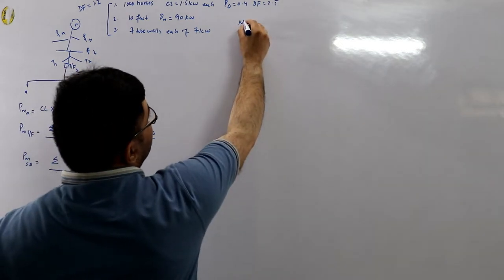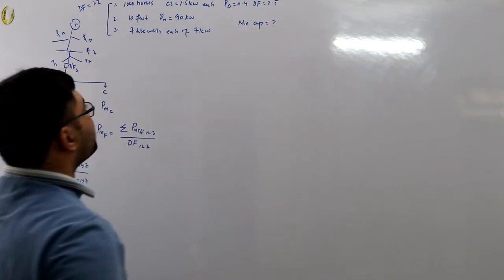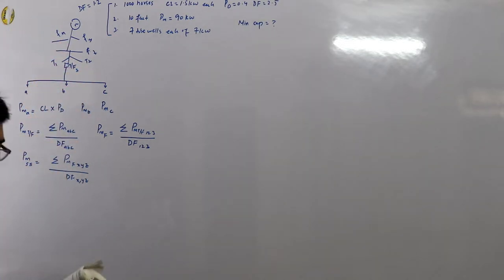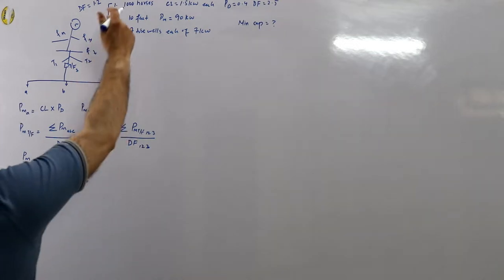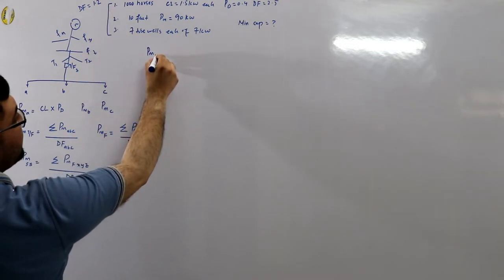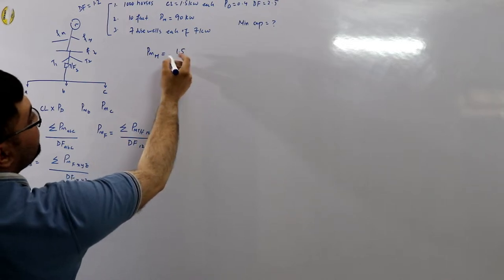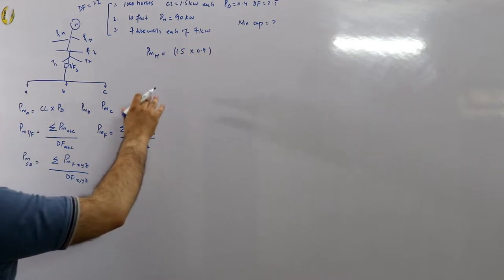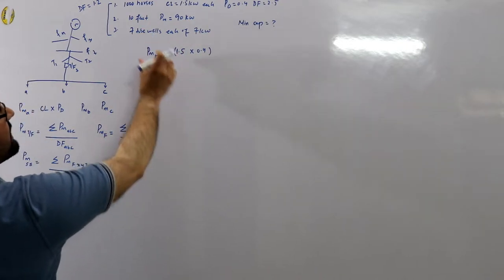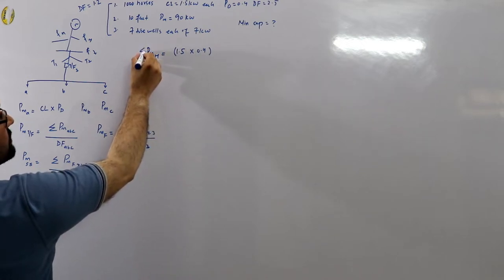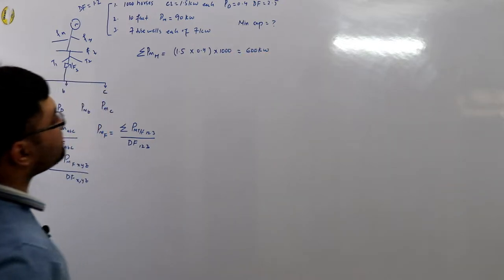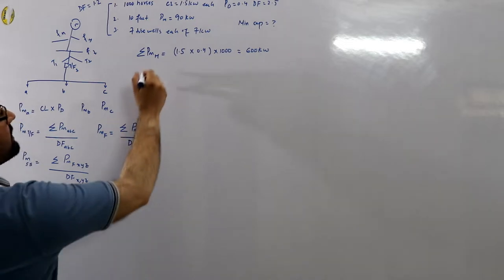We need the minimum capacity of the power station, which equals the maximum demand on the power station. First, find the maximum demand of the houses: 1.5 kilowatts connected load multiplied by the demand factor 0.4, then multiplied by 1000 houses. This gives 600 kilowatts as the summation of the maximum demands of the houses.